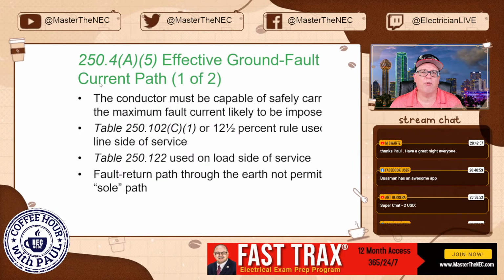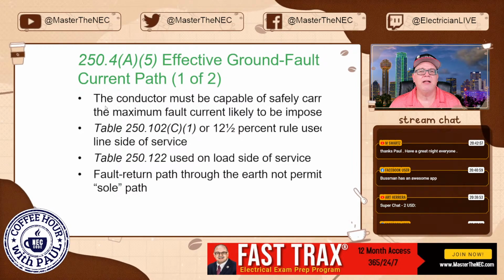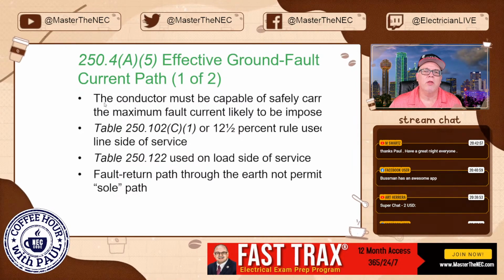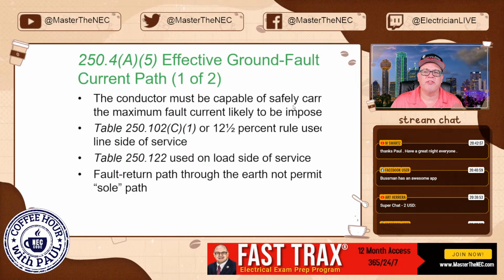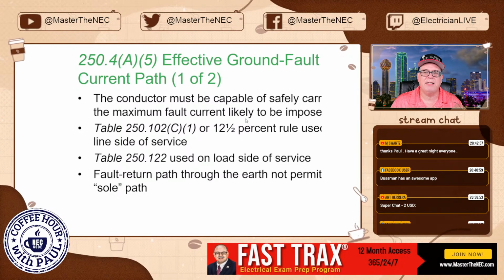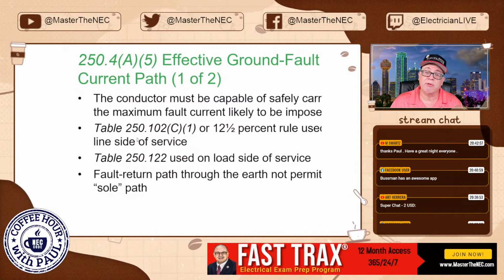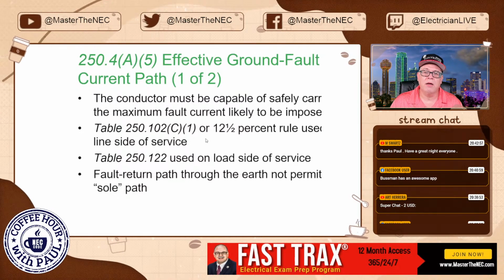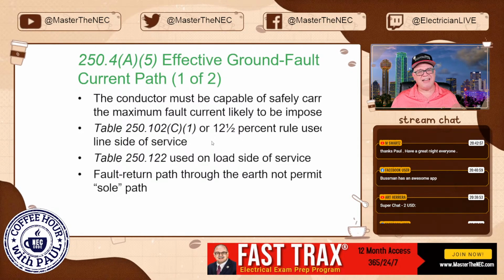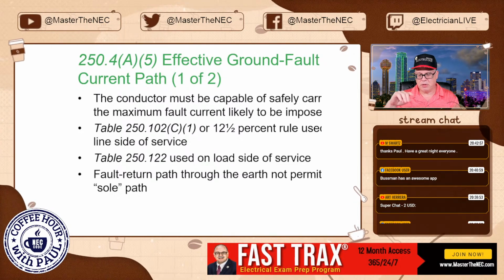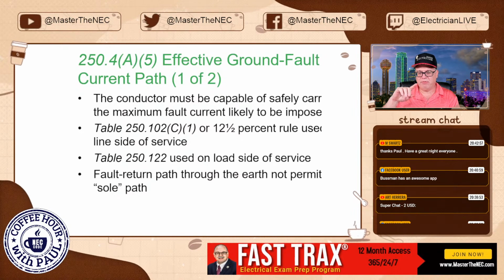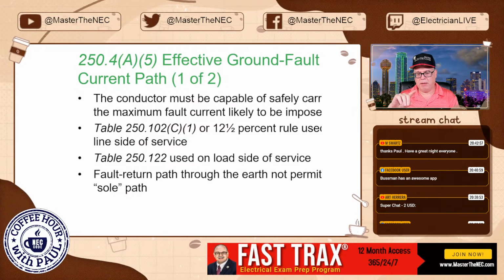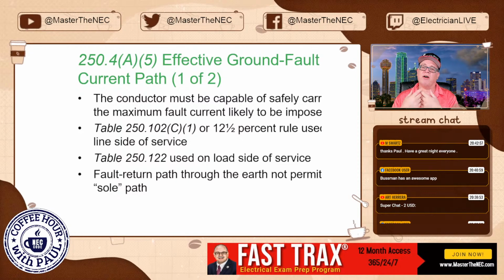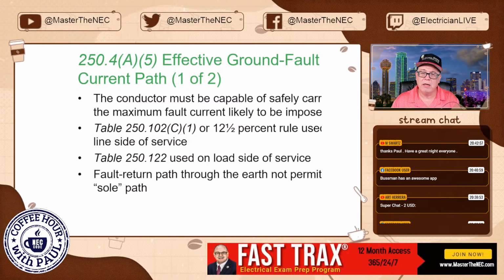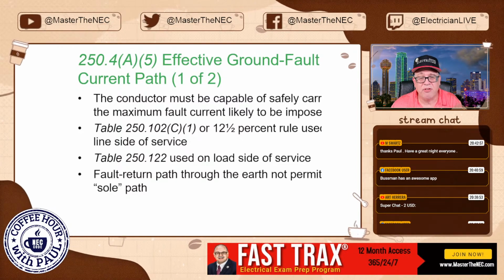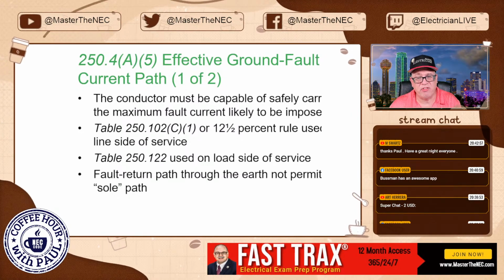All right, 250.4A5, effective ground fault current path. How do we accomplish this? So, the conductor must be capable of safely carrying the maximum current likely to be imposed on it. Table 250.102C1 is going to talk about sizing things like main bonding jumpers, system bonding jumpers, minimum sizes for grounded conductors, all of that type of thing. That is all what's covered in 250.102C1. And when you get over a certain size, you're going to have to go to a 12.5% rule, okay?